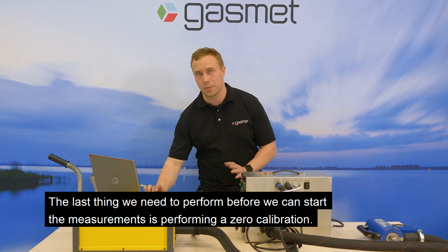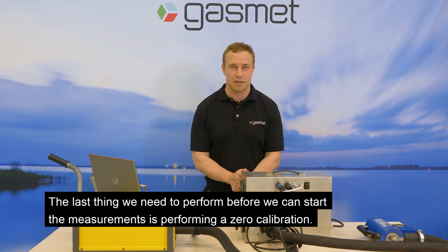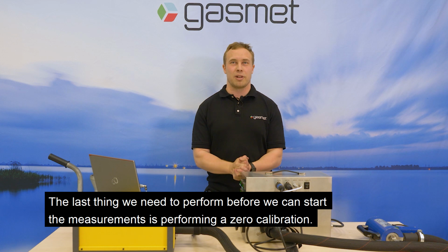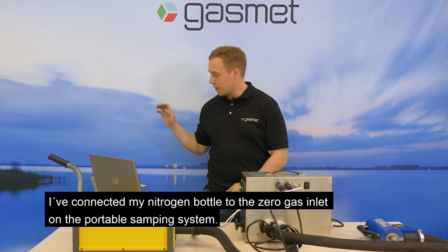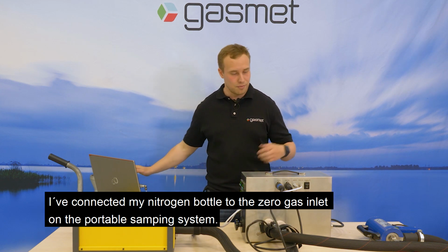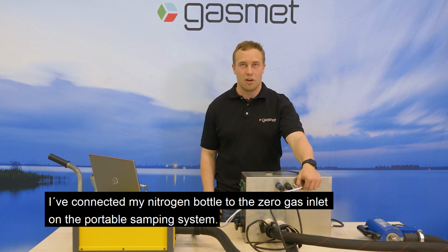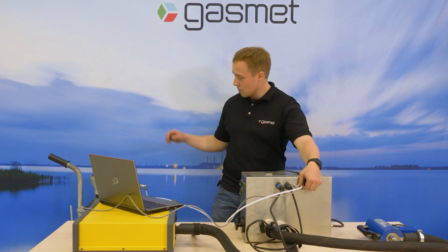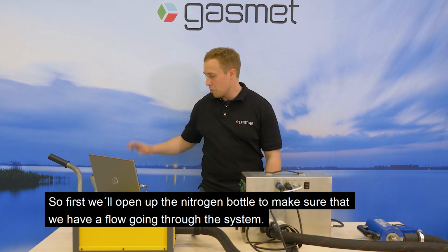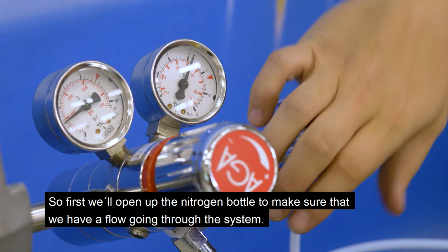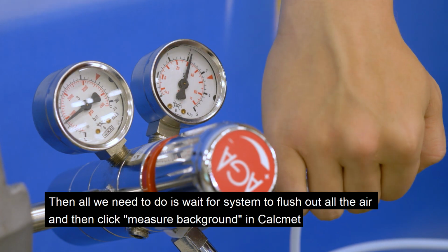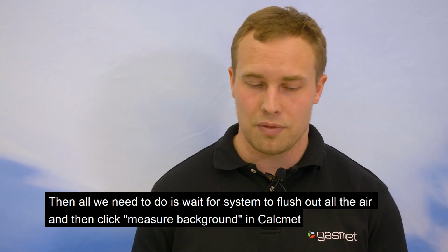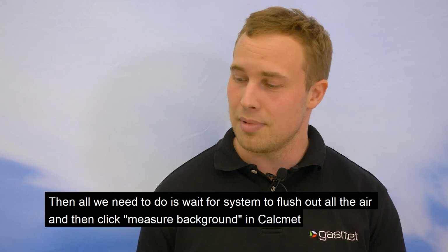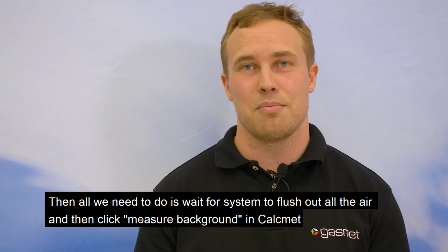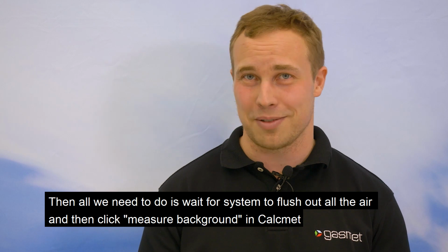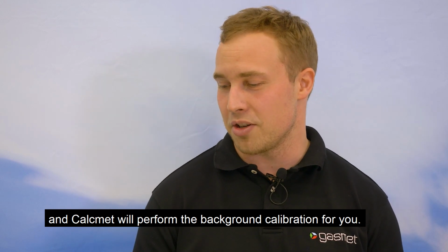The last thing we need to perform before we can start the measurements is a zero calibration. I've connected my nitrogen bottle to the zero gas inlet on the portable sampling system. So first, we will open up the nitrogen bottle to make sure that we have a flow going through the system. And then all we need to do is wait for the system to flush out all the air and then click measure background in Calcmet, and Calcmet will perform the background calibration for you.